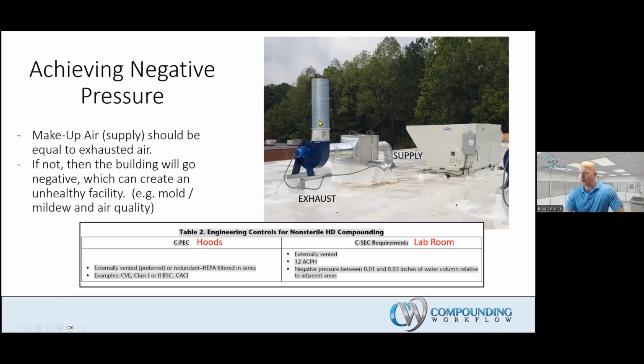The more air you exhaust out, the more air you've got to make up to put right back in it. So this system is then actually conditioning all of that outside air to put it into your clean rooms at, say, 64 degrees. Because by the time you put technicians in rear tying gowns, double shoe covers, double gloves, hair bouffant, and mask, they want it pretty cool in there. And so that takes a dedicated makeup air unit. There's nothing about an existing HVAC system on your commercial facility that was ever meant to do this. So there's no easy pass here, right?